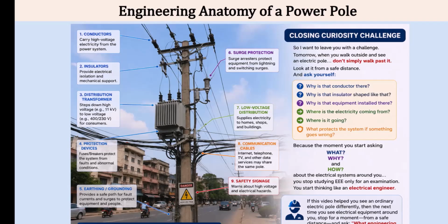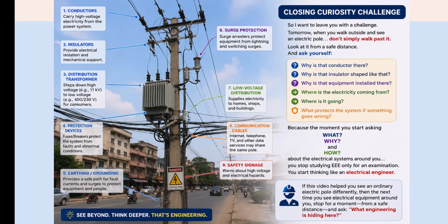What changed is what you are able to see in it. Now you are starting to see a system. You can look at the conductor spacing and think about electrical clearance. You can look at the insulator and think about insulation and creepage distance. You can recognize the transformer and understand why voltage transformation is necessary. You can identify protection equipment and think about what happens when a fault occurs.